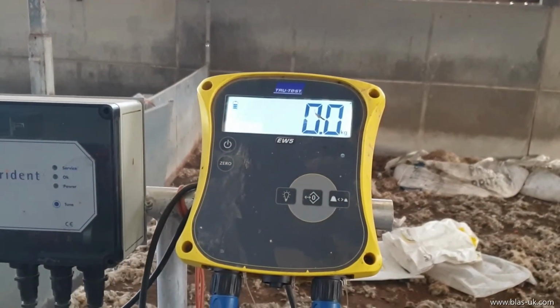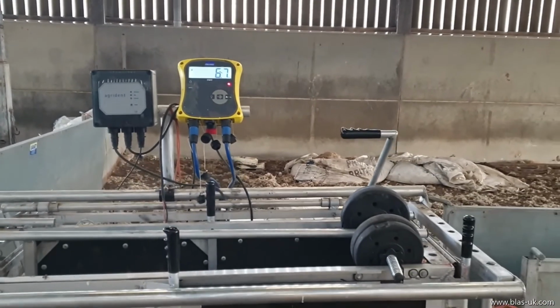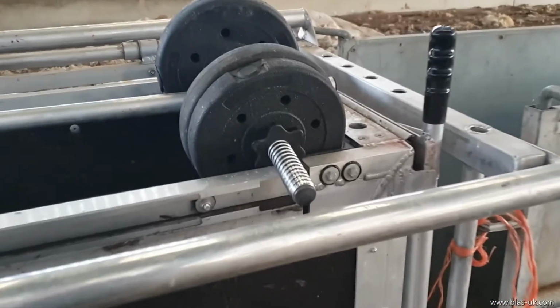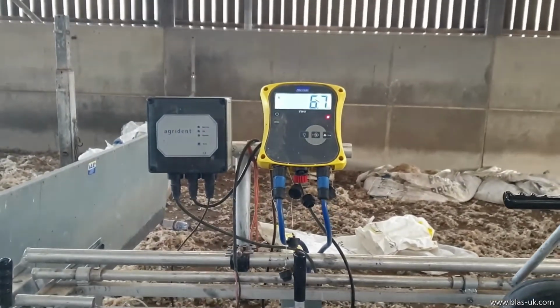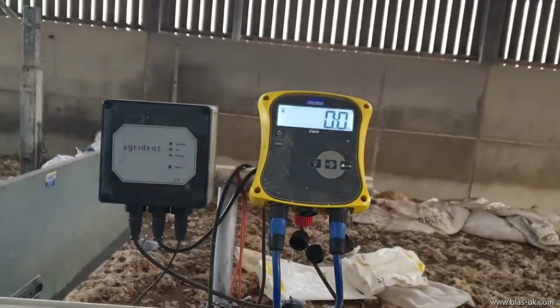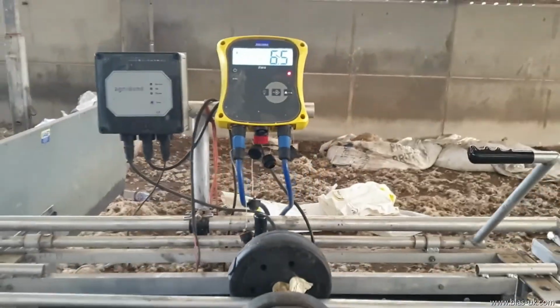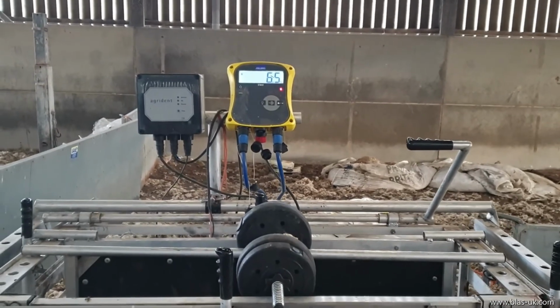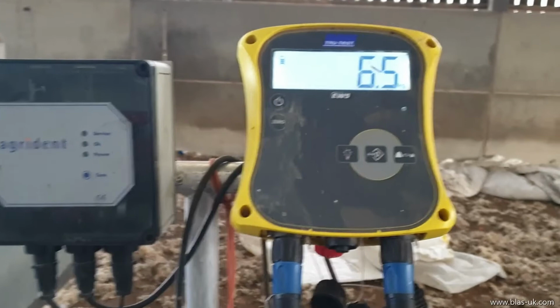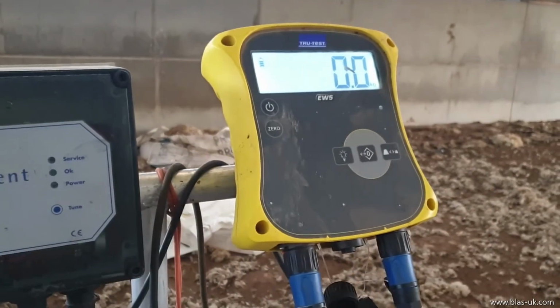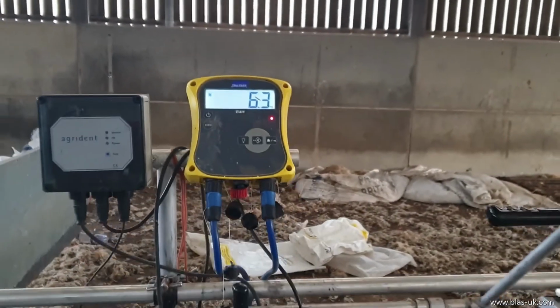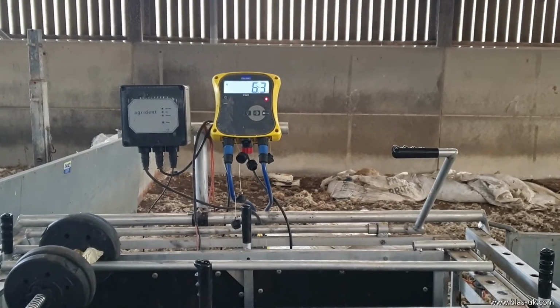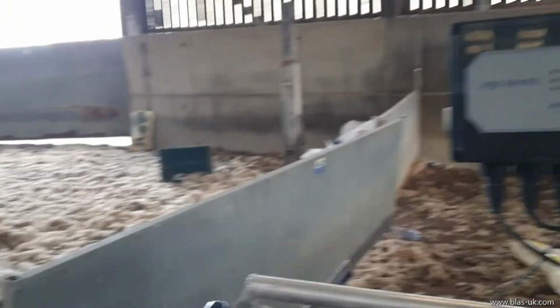Start with the zero on the weigh scales, put the weight on the end. It's not touching the isolation frame anywhere, so it's just weighing on the thing, and we've got 6.7. We take the weight off and let it go to zero, so we've got no weight on. Put the weight into the middle. We're now at 6.5. Again, if we take the weight off, let it go to zero. Put the weight on the opposite end. We've got 6.3. Back to zero.